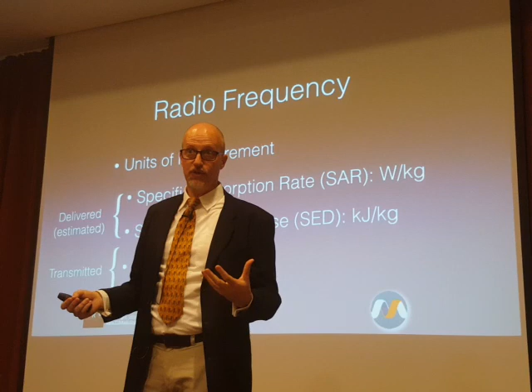And I've already told you that they vary tremendously just between and among systems. For that reason, we're beginning to see more and more MR systems and implants and devices that, instead of giving a specific SAR value, may have a B1 plus RMS value, or they may cross-list between the two. B1 plus RMS and SAR work on different principles, and you can't translate readily from one to the next. They're independent calculations. So 2 watts per kilogram does not translate to 2 microtesla of B1 plus RMS, and there's not a conversion factor. You really need to look at them as independent values.